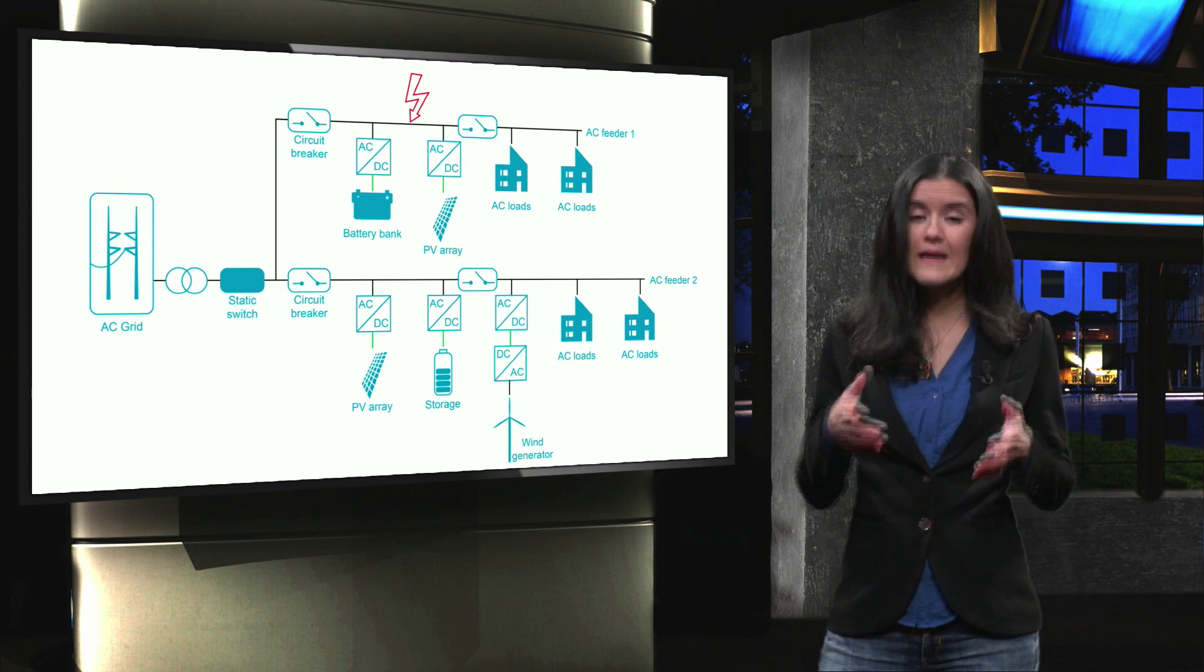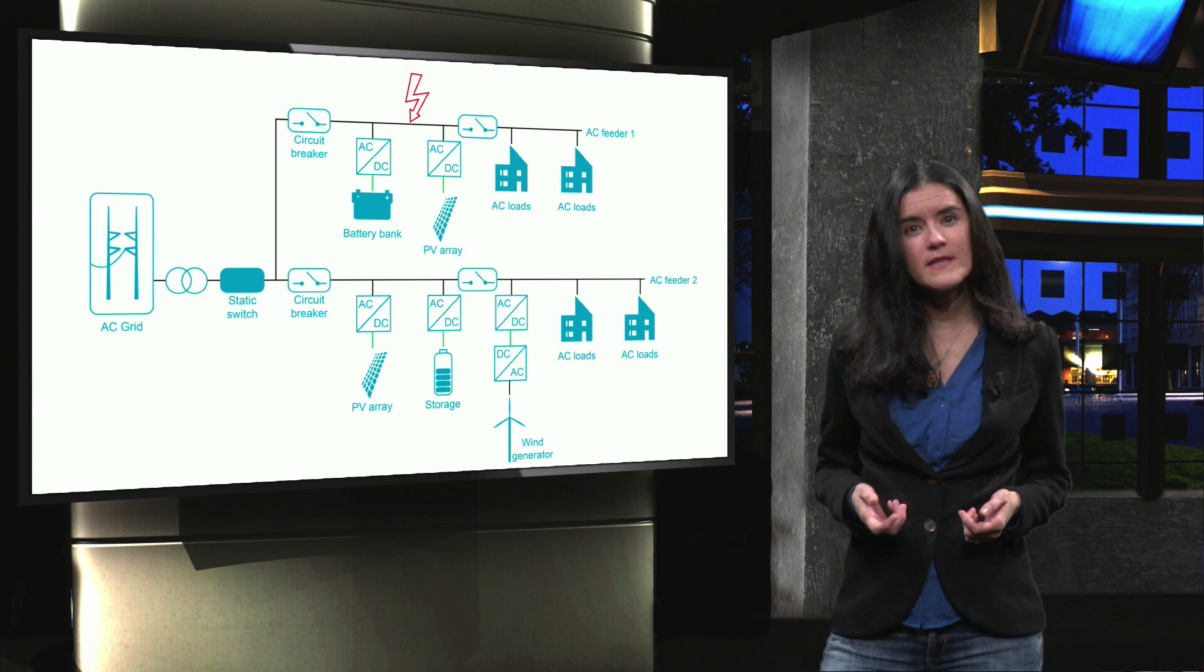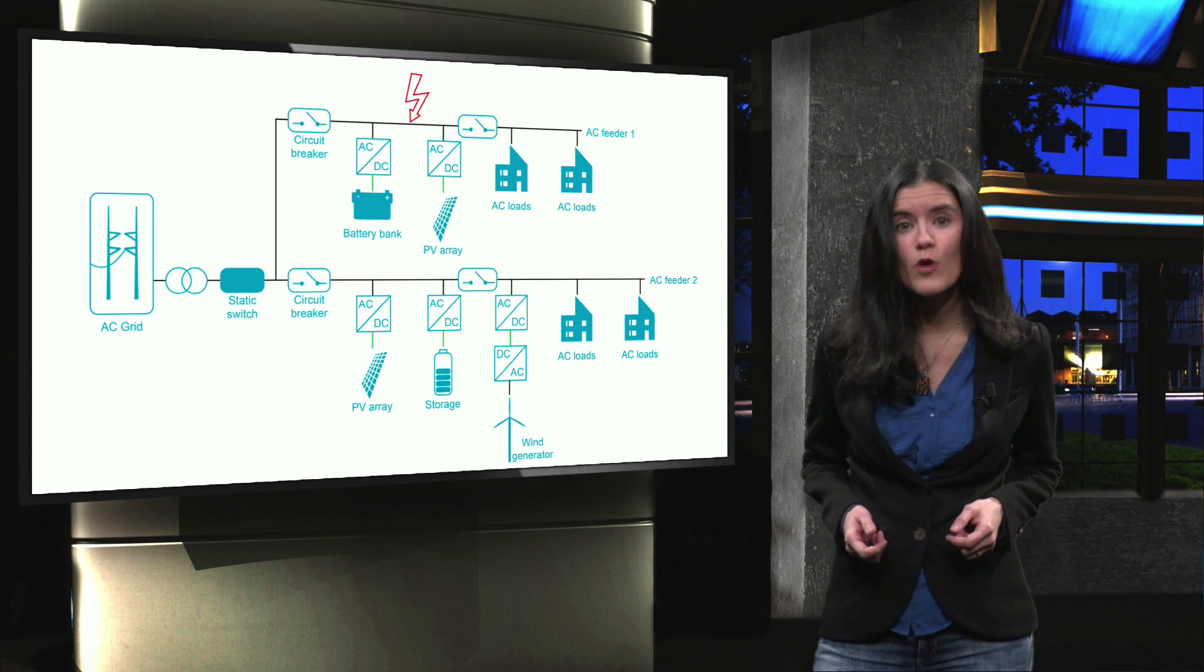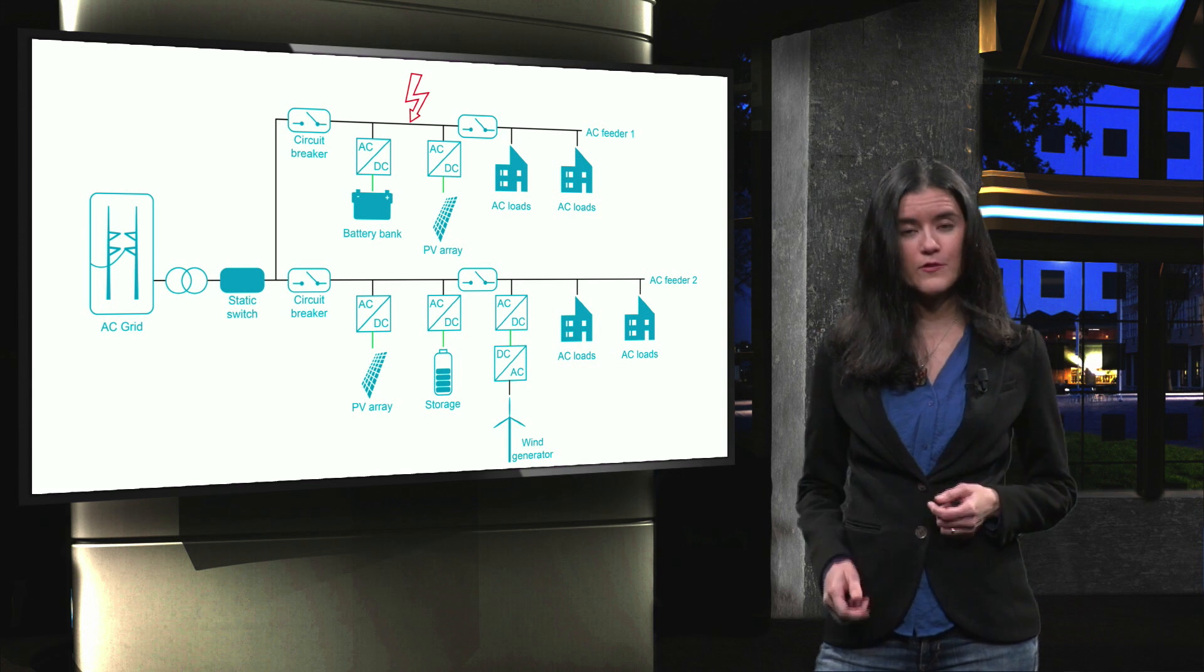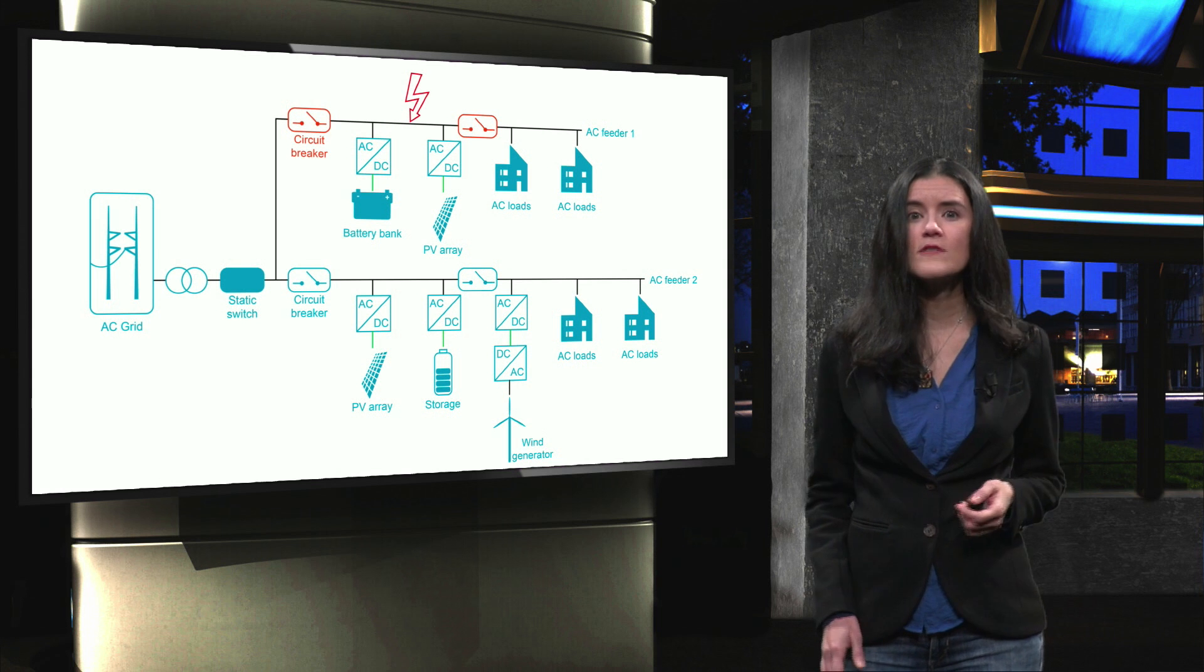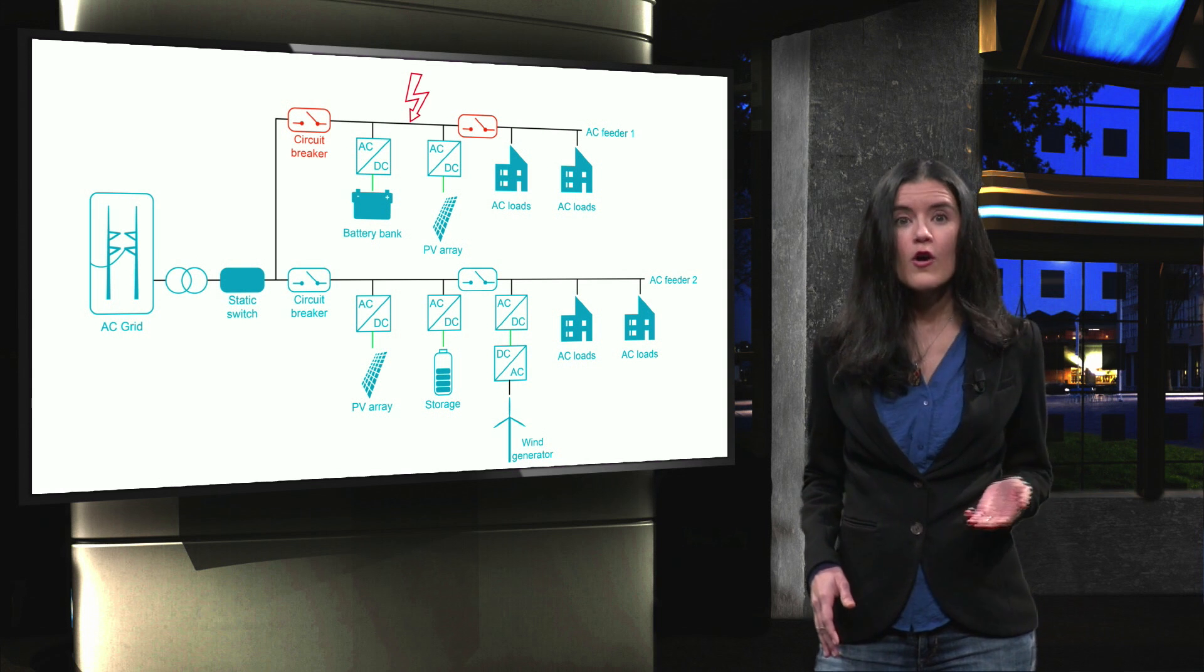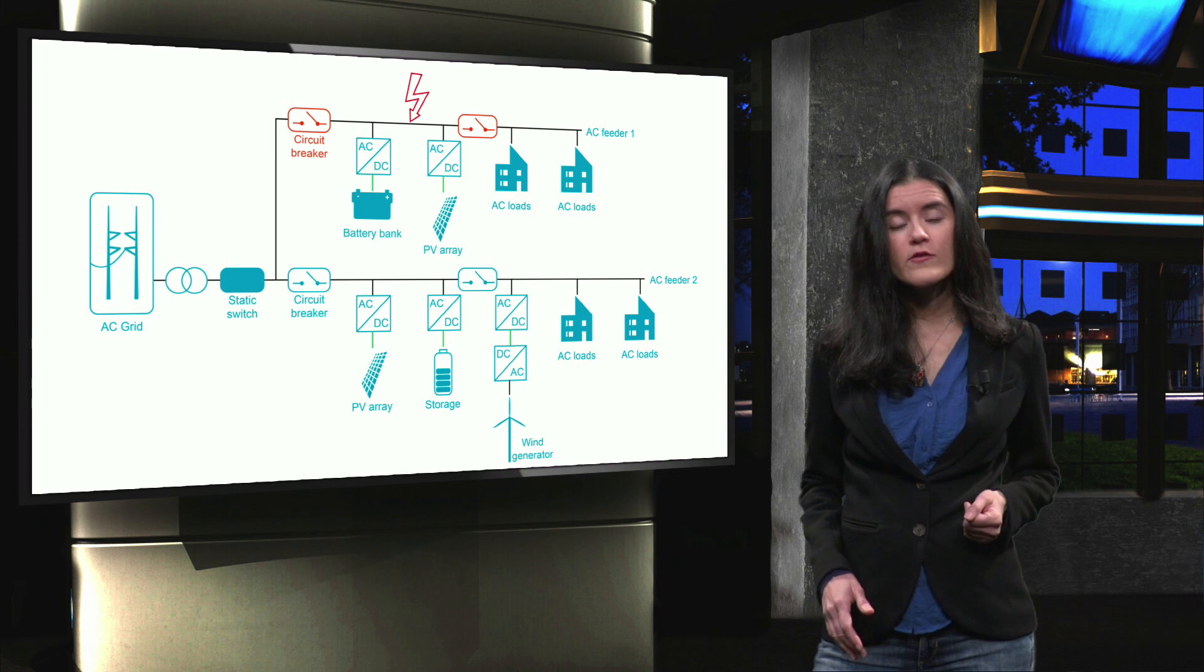On the other hand, if the fault occurs inside the microgrid, the protection scheme will aim at isolating the smallest possible area of the distribution feeder. This is intended to reduce the negative impact of the fault on the operation of the microgrid to the minimum.